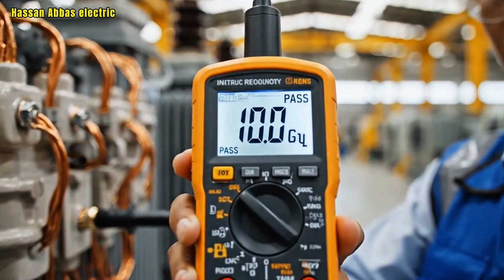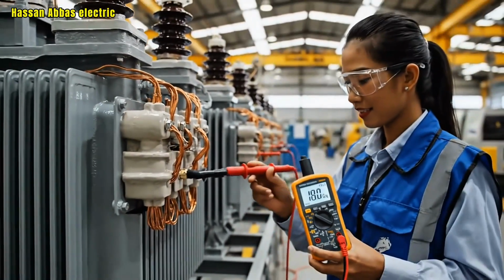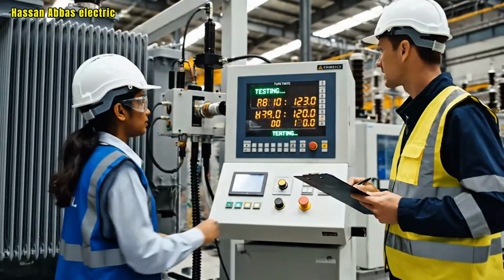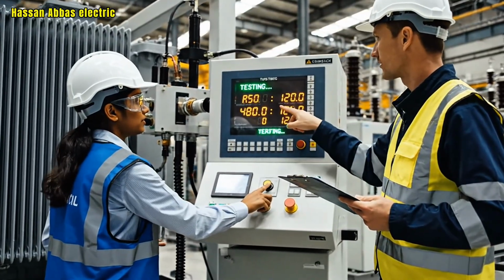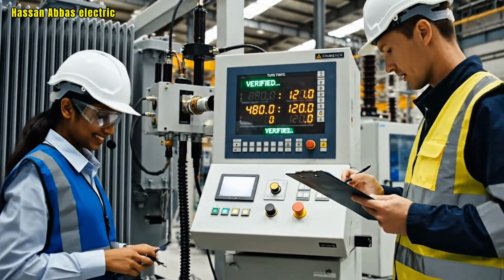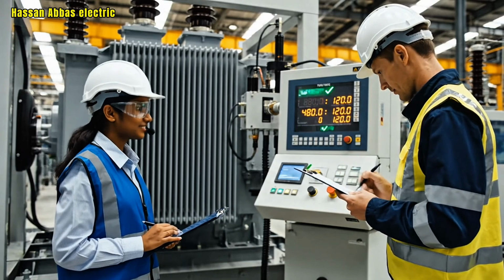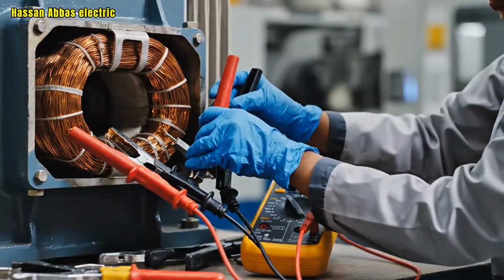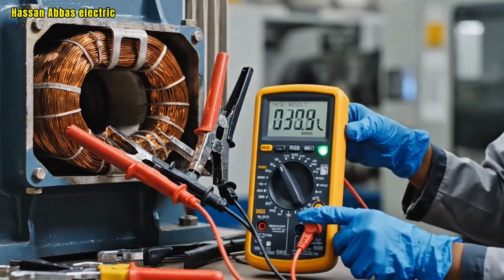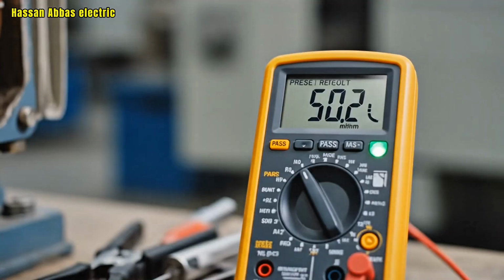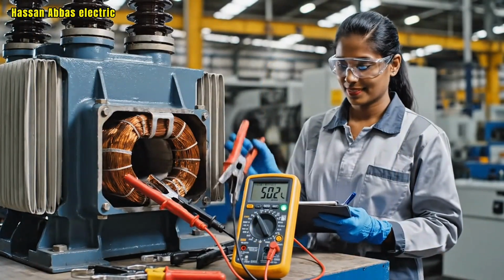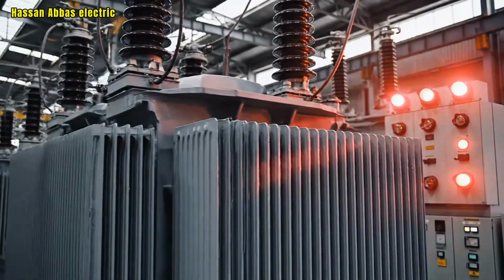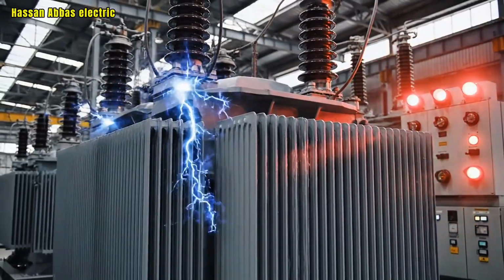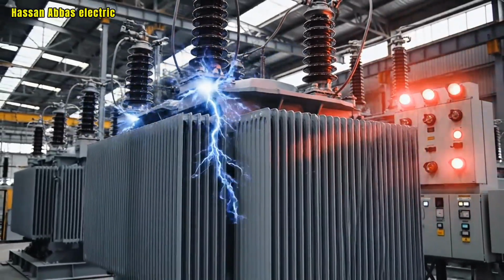Insulation resistance is tested to ensure electrical safety. Turns ratio testing confirms correct voltage transformation. Winding resistance is measured to detect internal defects. High voltage testing ensures the transformer can handle stress safely.